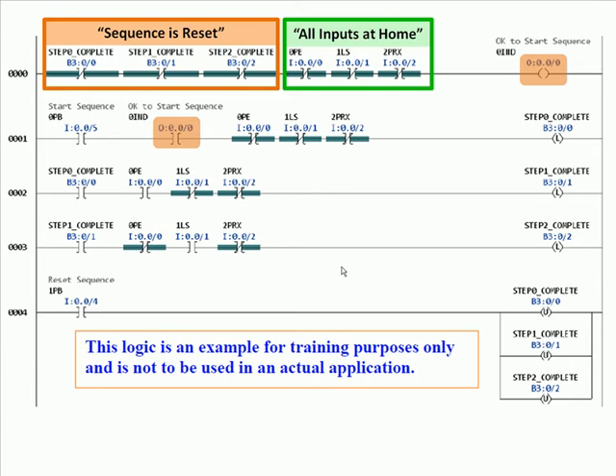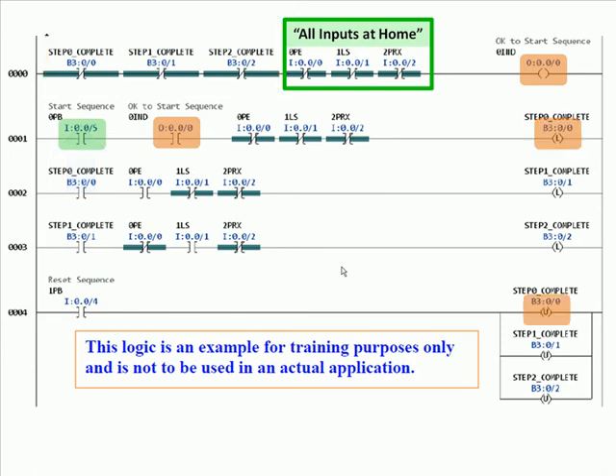Once the sequence is ok to start, if you push push button 0 and you're still in the home position, step 0 goes complete. Notice that when step 0 went complete, b3/0/0 — anywhere it was examined-off — is now false, so rung 0 is now false and 'ok to start sequence' has been set to 0. Rung 1 is also false. However, we have latched in the condition 'step 0 complete' because the conditions that made it complete are no longer true — that's why we need to latch it. In rung 2, everything is true with the exception of photo eye — we're waiting for photo eye to be true.